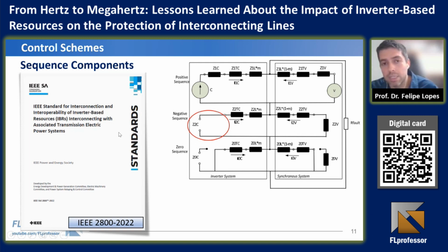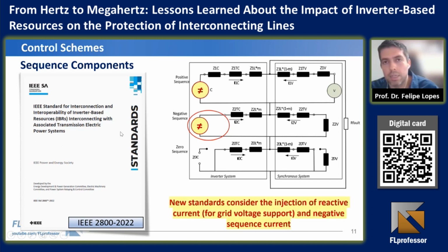And this is very interesting because this new standard leads us to think differently. It was inspired by the VDE grid code from Germany, which was already programmed to inject reactive current for grid support, voltage support. But it now also includes negative sequence current injection. So grid following technologies are still seen as current sources, but different components are injected in order to improve the behavior of protection and the behavior of the system as a whole.